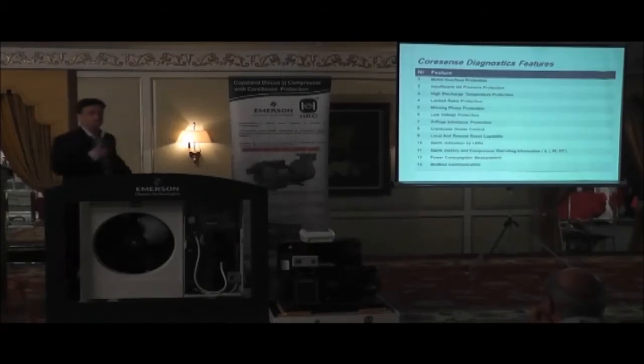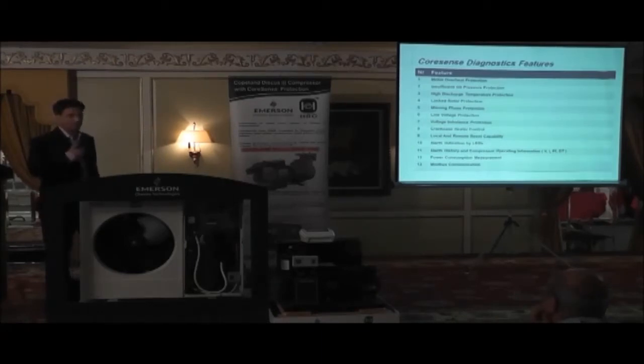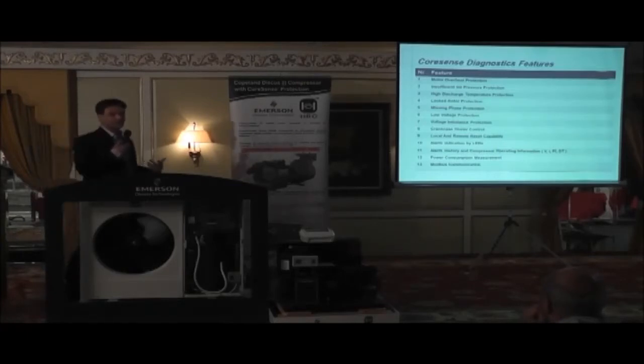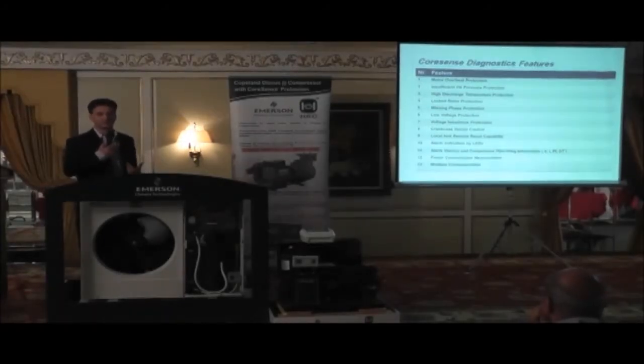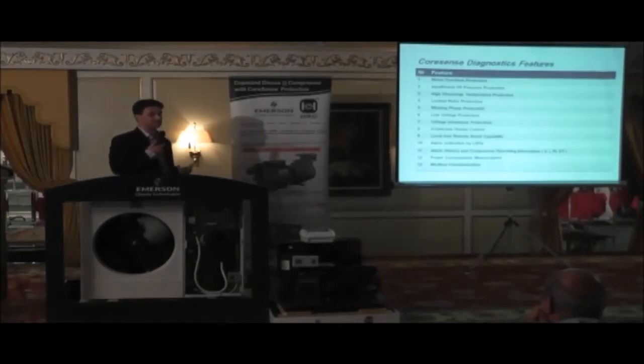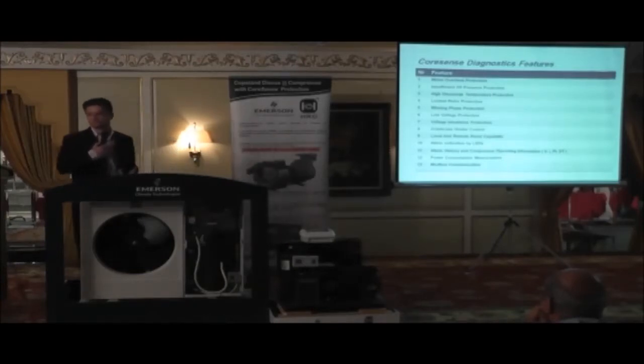So number 1 and 2 is what we were offering before. Number 3, now we include high discharge temperature protection. So this is to prevent the compressor from overheating. When we did a survey in the US, almost 35% of semi-hermetics that were damaged in the field, that were returned to the factory, had failed because of overheating. So this is a very low-cost technology to apply to the compressor to protect the compressor in the field.